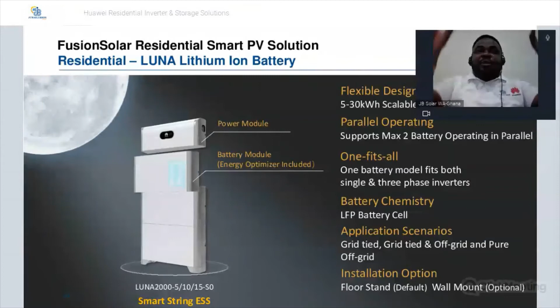You can have one power module and 3 battery modules, that's 15 kilowatt hours. So one battery rack is 15 kilowatt hours maximum. For every Huawei inverter in the system, from single phase to three phase, the maximum battery modules they can take is 2 racks. So one inverter can take 2 racks in parallel, which means the maximum one inverter can take is 30 kilowatt hours.